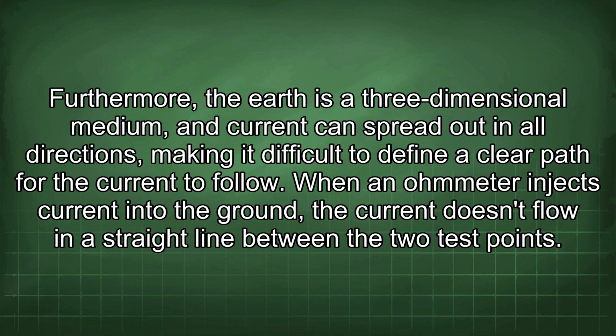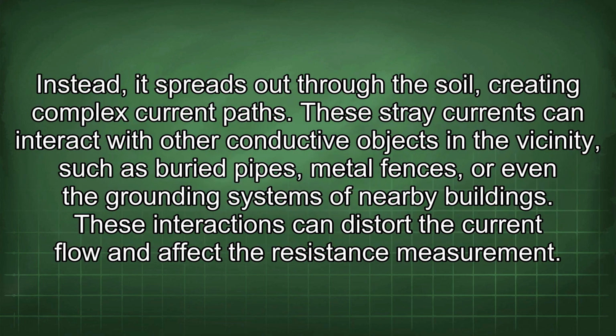When an ohmmeter injects current into the ground, the current doesn't flow in a straight line between the 2 test points. Instead, it spreads out through the soil, creating complex current paths. These stray currents can interact with other conductive objects in the vicinity, such as buried pipes, metal fences, or even the grounding systems of nearby buildings. These interactions can distort the current flow and affect the resistance measurement.